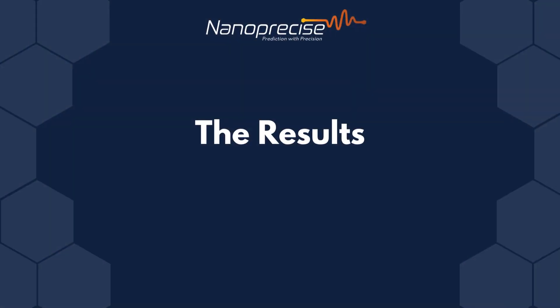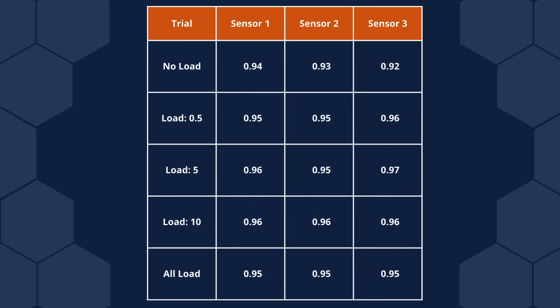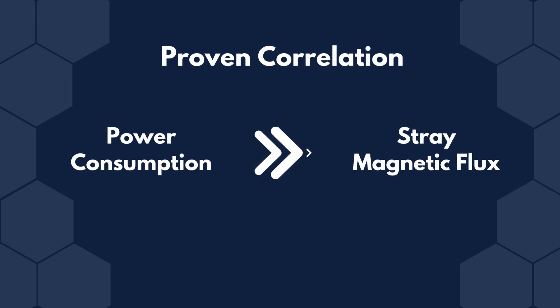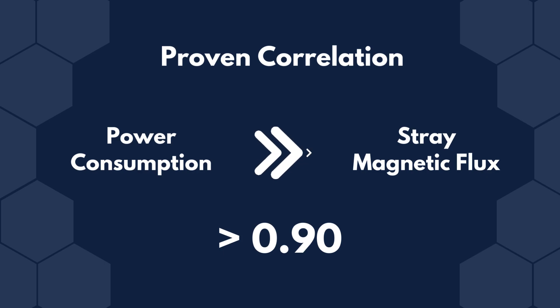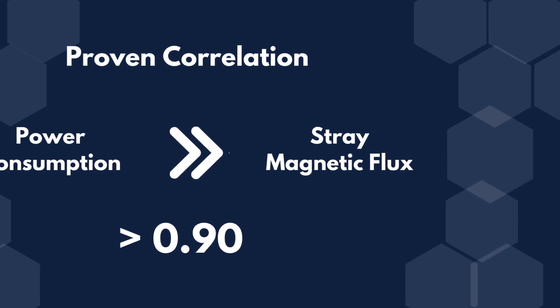Across a total of 134 trials, which included varying loads and RPMs, the Machine Doctor sensors were able to detect a statistical correlation between stray magnetic flux and power consumption. On average, the tests delivered a correlation coefficient of greater than 0.95, denoting a very strong correlation between the two.